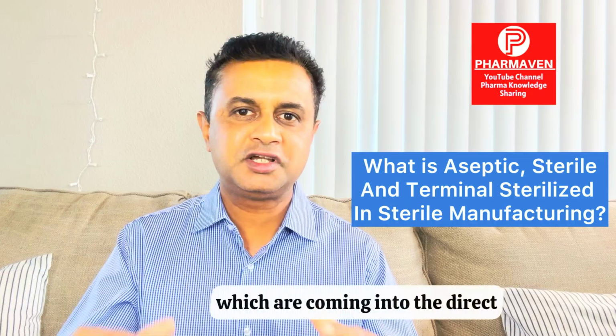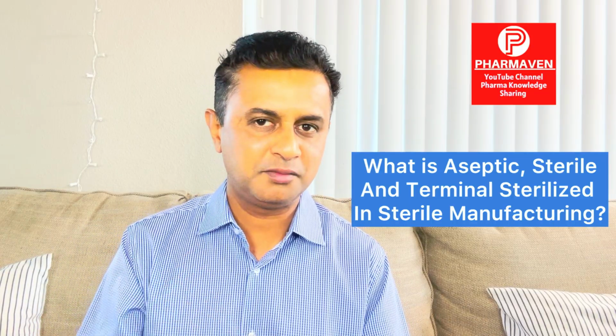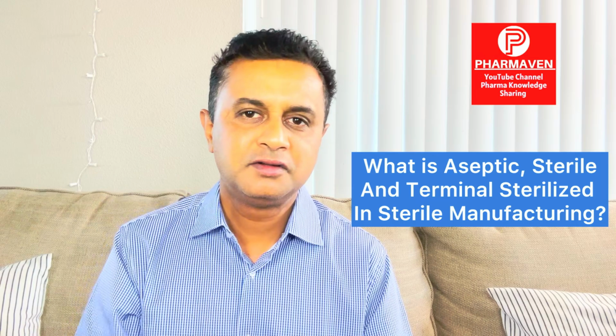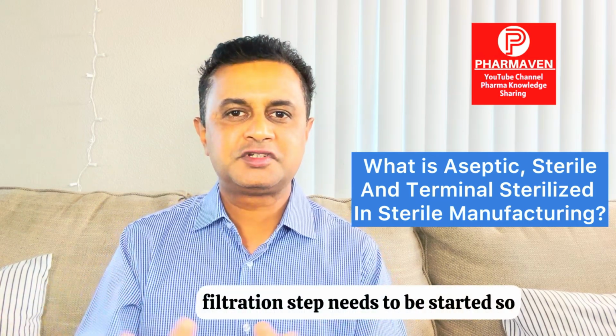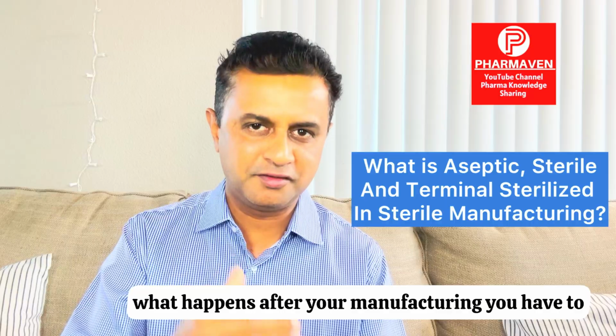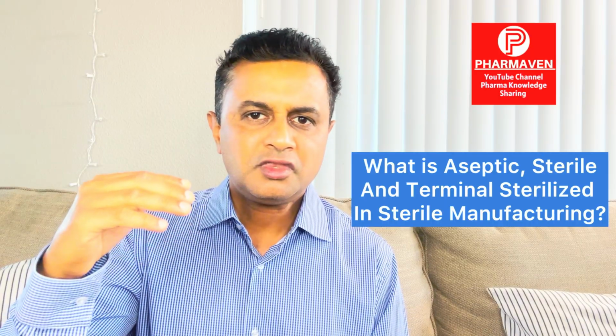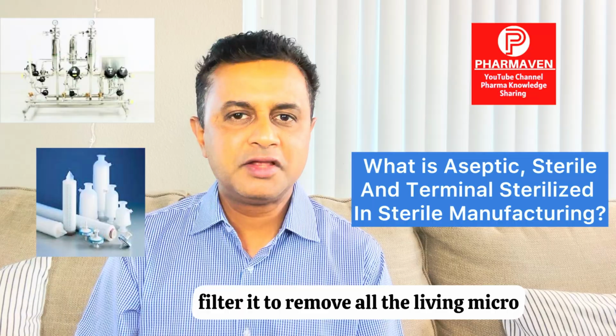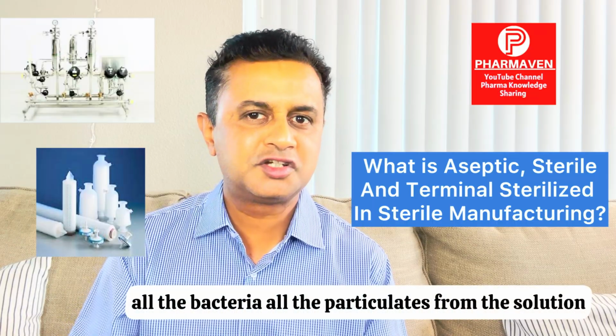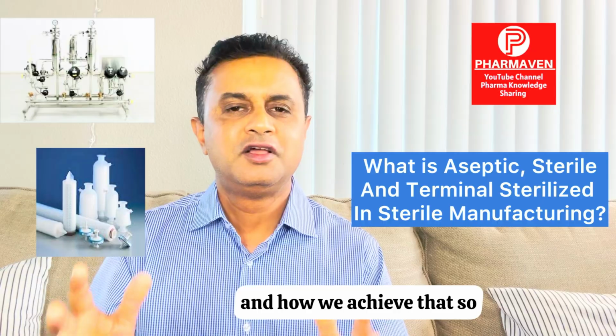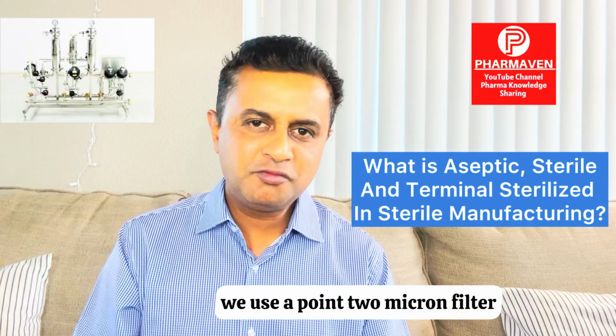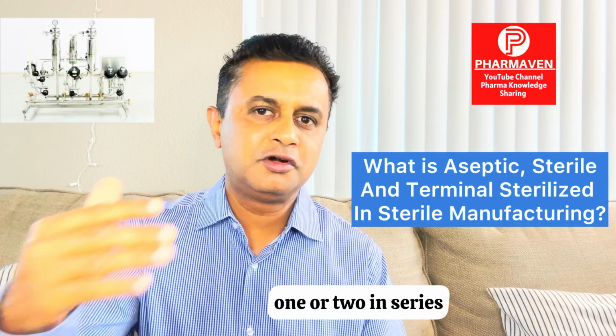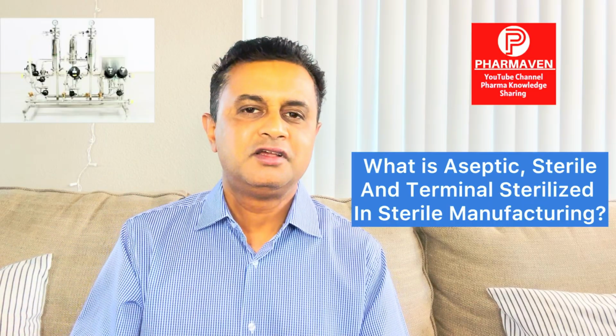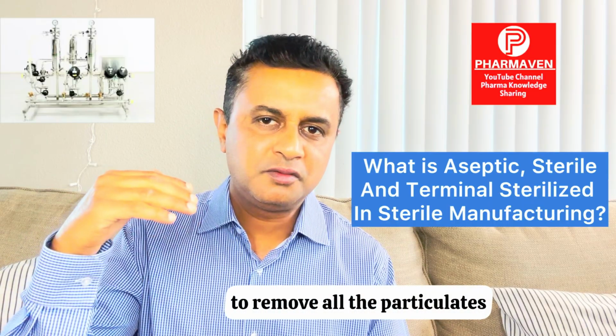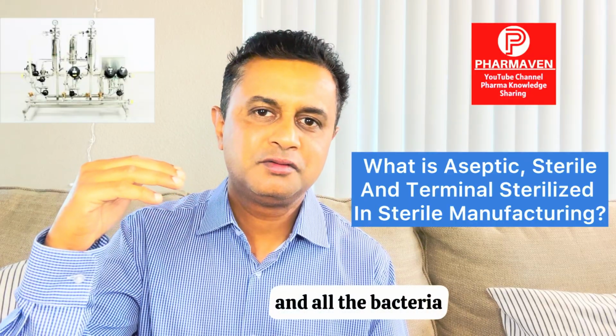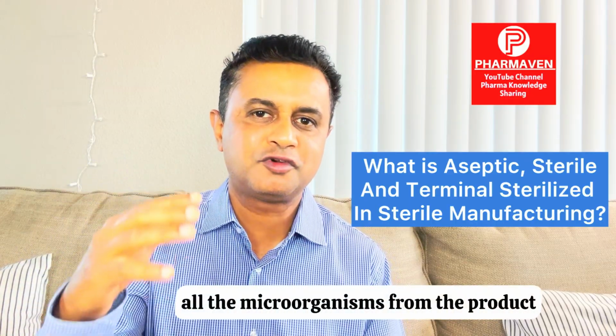All the components which come into direct product contact after the filtration step need to be sterilized. So after manufacturing, you have to filter the solution to remove all the living microorganisms, bacteria, and particulates. We achieve this using a 0.2 micron filter, one or two in series, to remove all particulates and microorganisms from the product.